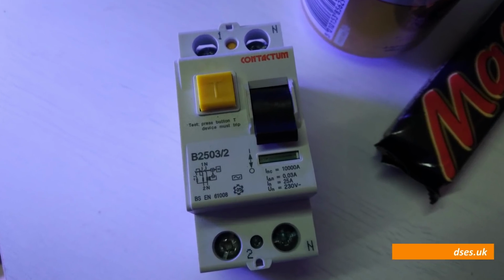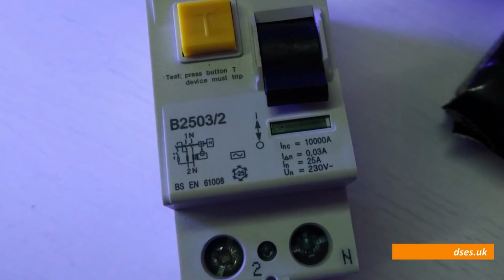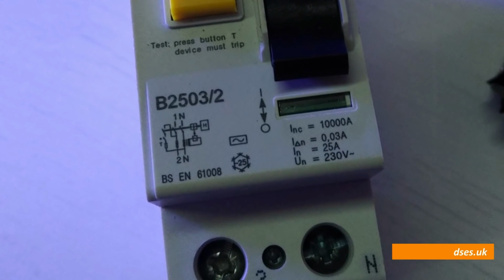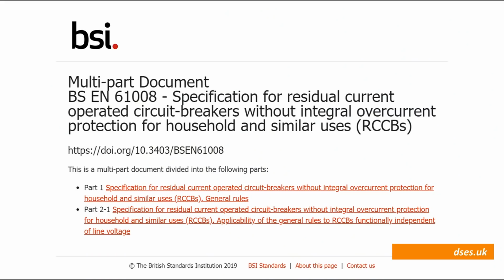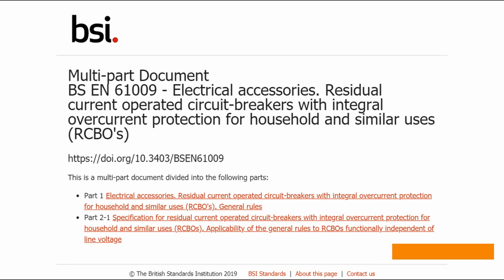So let's go and see what we can see with this, shall we? We can see it's definitely a 61008 device, and if we look up BSEN 61008, that's the specification for residual current operated circuit breakers without integral overcurrent protection, unlike 61009, which is for residual current operated circuit breakers with integral overcurrent protection.